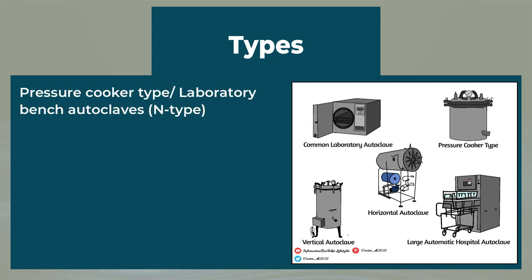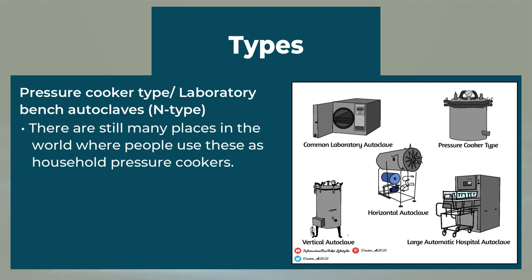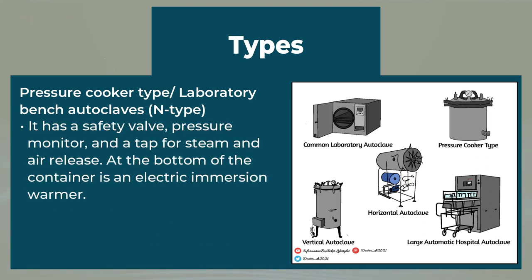Now let's see the types of autoclave. There are several different types available, including the pressure cooker type, also known as laboratory bench autoclaves. These are still used in many places as household pressure cookers. A more contemporary version has a metal compartment with a secure metal dock that can be closed using a rubber gasket. It has a safety valve, pressure monitor, a tap for steam and air release, and an electric immersion heater at the bottom.